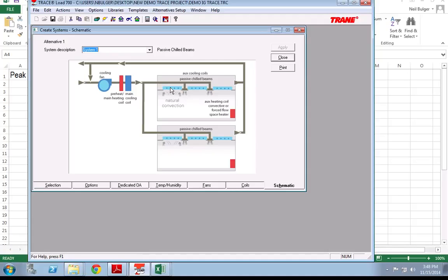And there might be some rooms on the west and the south that need a lot more cooling than that, because that's where the sun might be, and maybe those rooms are peaking around 20 or 30 BTUs a square foot. And so it can be risky if you just size the entire building after running the loads and say, well, all the spaces, we're first going to say the radiant contributes this much, and whatever is left over when the building peaks is the size of the coil for the air handler.